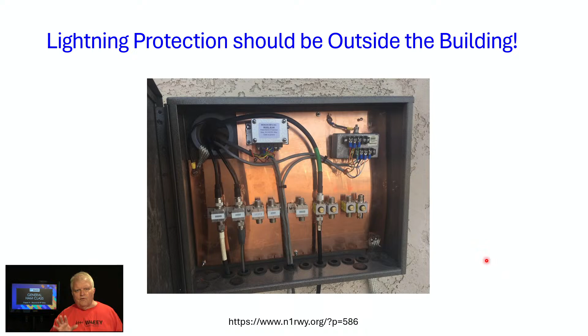These are surge arresters for antenna lines here. These have gas discharge tubes inside that will clamp the line if it detects voltage over a certain threshold. And that clamping action can help prevent lightning damage to equipment. If you're going to put one of these systems in, make sure that it's installed outside the building. You do not want to invite lightning inside your building, and all of the grounding and straps and whatnot should be outside.